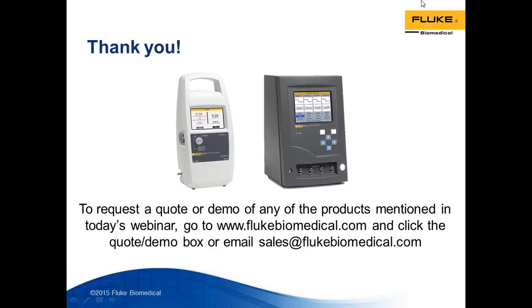All righty, next one. Does the ID8 family require distilled water for testing? We recommend distilled or deionized water, yes, because like I had mentioned, there is a burette inside the product. So just to make sure that the electronics are always clean, and there's no impact. We highly recommend deionized or distilled water because there can be essentially residue inside. So if you use distilled and deionized water, the product is going to last you a long, long time. And typically our products, they go for decades. So it's a practice that we recommend to our users to make sure that the products are within accuracy, function well.